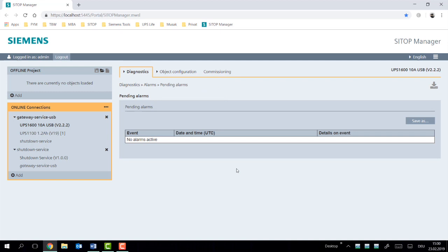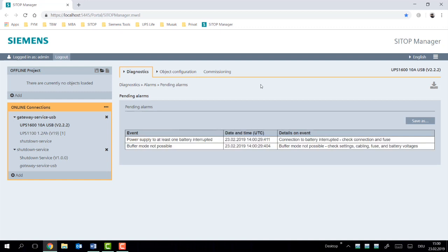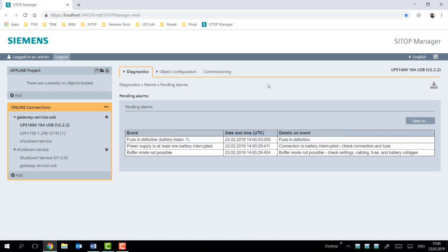Let me pull the fuse on the SITOP UPS 1100 battery and see if we can generate an active alarm. What we have here already, so immediately it shows us some of the active alarms.